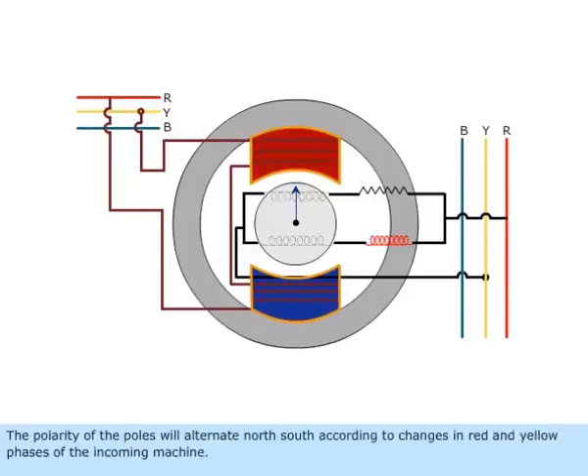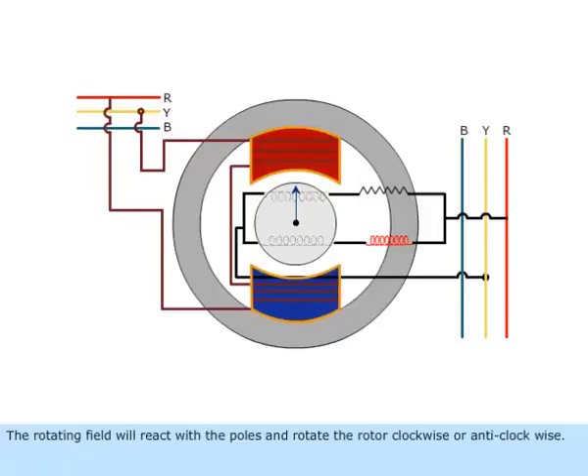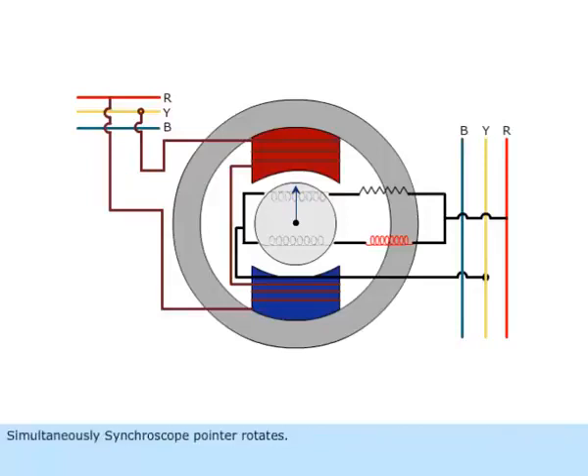The polarity of the poles will alternate north-south according to changes in red and yellow phases of the incoming machine. The rotating field will react with the poles and rotate the rotor clockwise or anticlockwise. Simultaneously, the synchroscope pointer rotates.